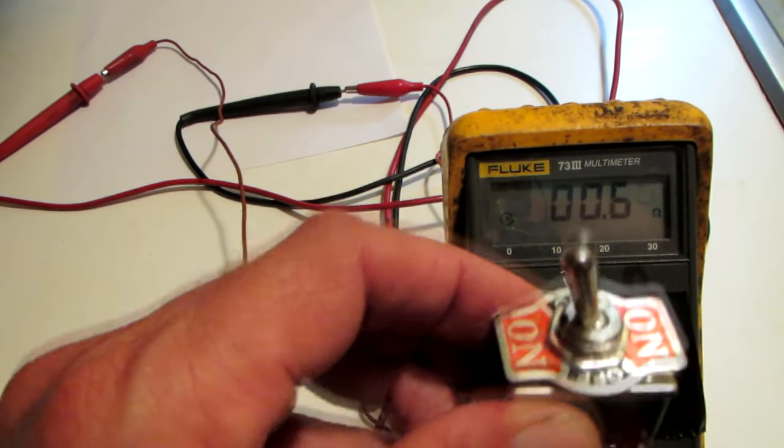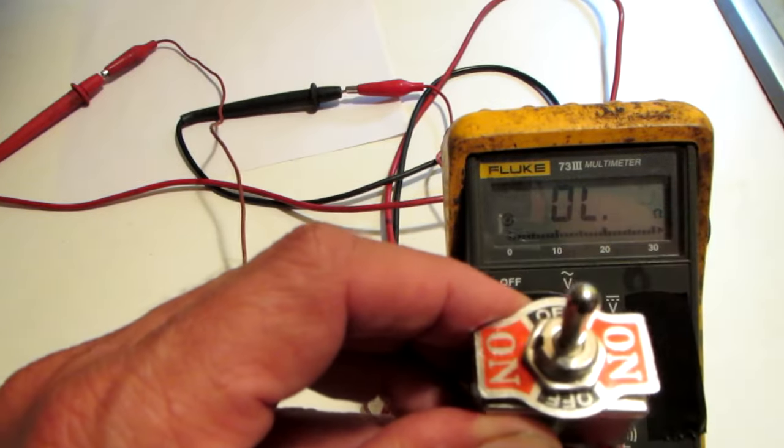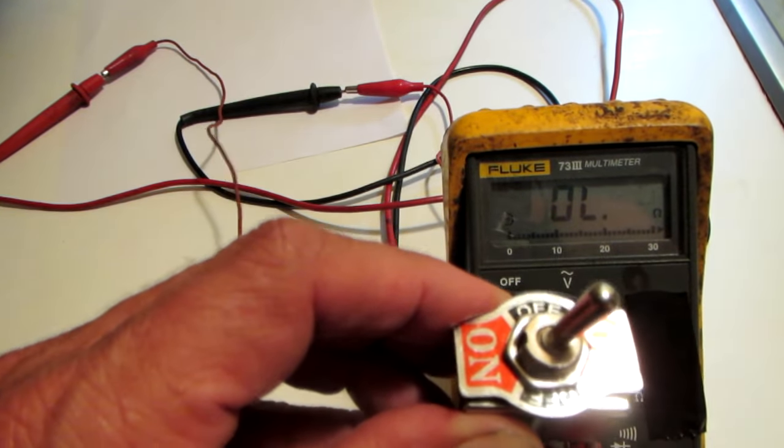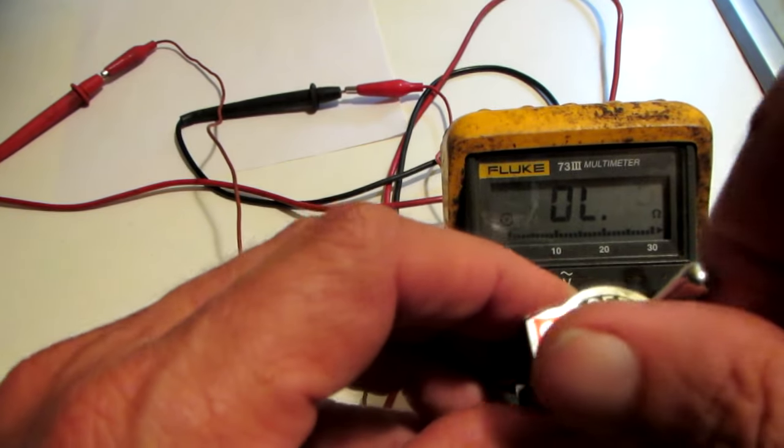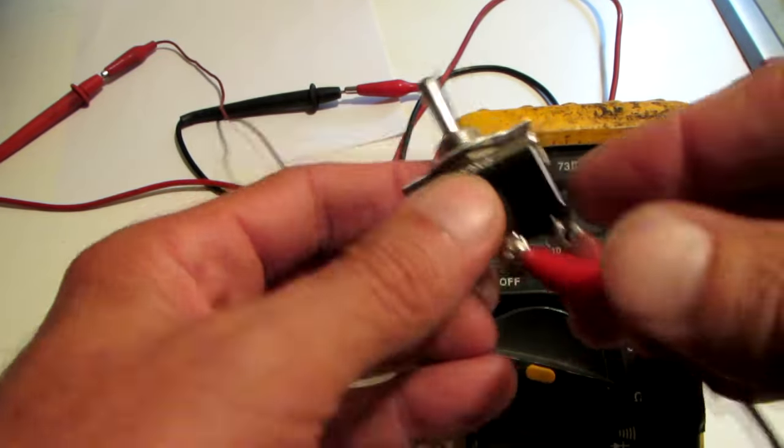The selector is in the off position. We're reading open. Put it to on. Read point four, point five. Back to off. Reads open. And throw it to the other side. Reads open. It's a good switch.